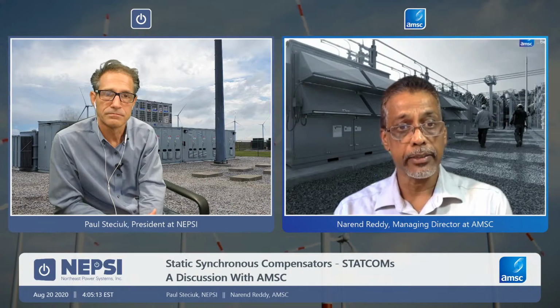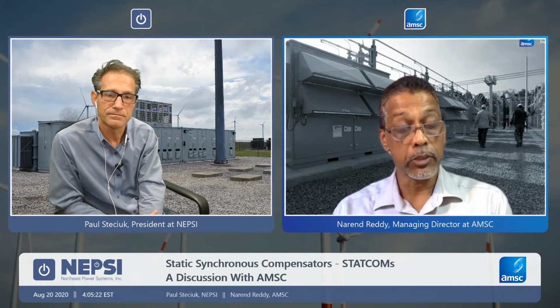So if there are a lot of distributed solar plants out in the distribution grid that are large enough and are affecting or could affect the level of flicker in the grid, and it's not tolerable by the customers or the utility, the dvar system can be very effectively used to address that. And so the question also is how large is the solar farm? How spread out are the solar inverters, and what capability can be harnessed for the grid requirements? At the end of the day, it's the performance of the grid that matters. Similar to how I talked about the wind farms, it's really about how the individual turbines or individual solar inverters can manage or not. And also the ability to have a park controller that can act fast enough overall to help address that.